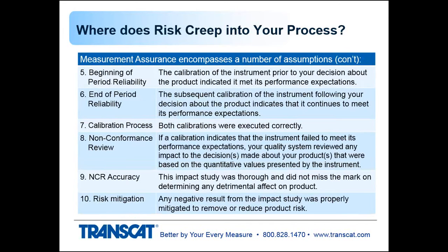Number five is beginning of period reliability, and that has to do with the calibration of the instrument and the way that it's left, the condition it's left in, for use during its calibration cycle. End of period reliability has to do with the subsequent calibration that tells you the condition or status of the instrument at that discrete point in time.